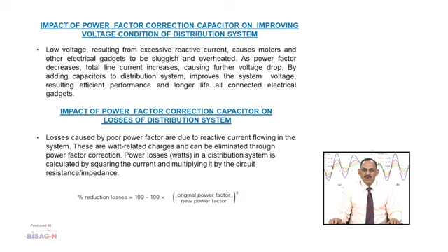Impact of power factor correction capacitor on losses of distribution system. Losses caused by poor power factor are due to reactive current flowing in the system. These are watt related charges and can be eliminated through power factor correction. Power factor losses in a distribution system are calculated by squaring the current and multiplying it by the circuit resistance or the circuit impedance. The formula for calculation of percentage reduction in losses equals 100 minus 100 into original power factor divided by new power factor, whole square. Thanks.